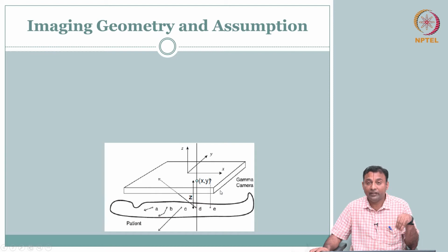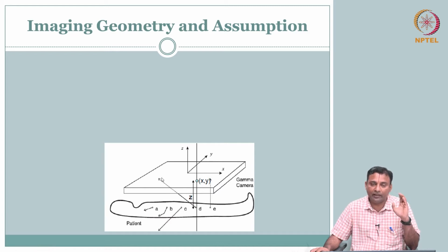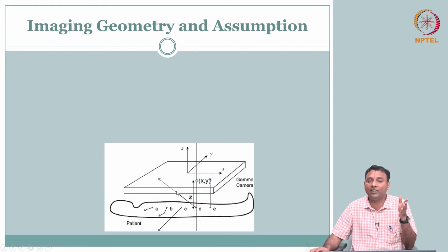Even there, it could probably go in a direction which is not hitting the detector perpendicular, right, in this manner. So remember, we had a collimator, and the collimator is looking for a straight line of sight. So even though it might go, in all likelihood the collimator will not take it, right.